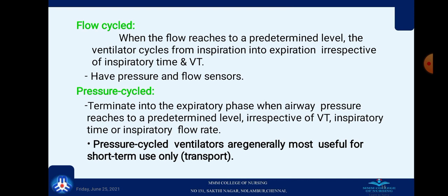Flow cycle: when the flow reaches a predetermined level, the ventilator cycles from inspiration into expiration irrespective of inspiratory time and VT, that is tidal volume. They have pressure and flow sensors. Then we discussed pressure cycle: it terminates into the expiratory phase when airway pressure reaches the predetermined level irrespective of VT, inspiratory time or inspiratory flow rate. Pressure cycle ventilators are generally most useful for short term use only, that is, during transportation.